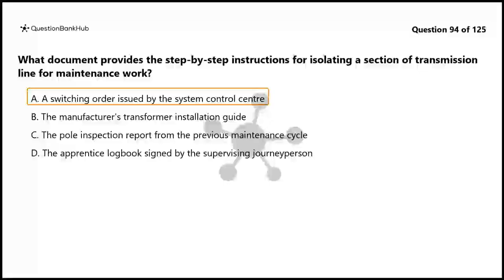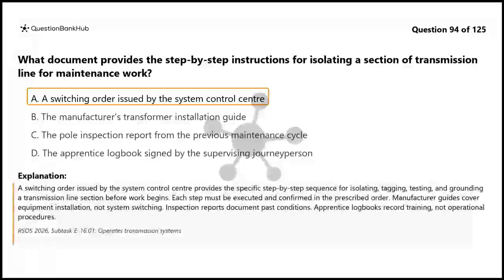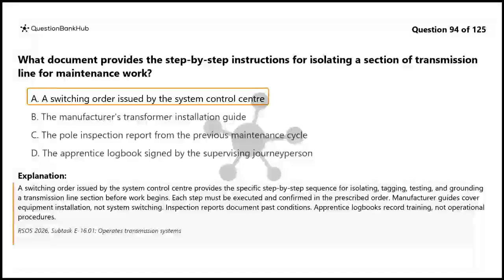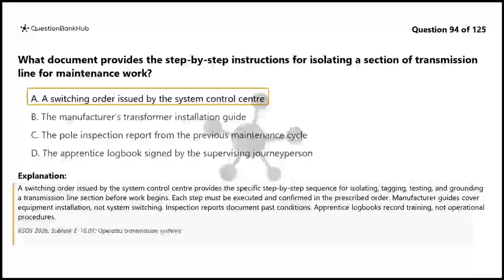The correct answer is A. A switching order issued by the System Control Center provides the specific step-by-step sequence for isolating, tagging, testing, and grounding a transmission line section before work begins. Each step must be executed and confirmed in the prescribed order. Manufacturer guides cover equipment installation, not system switching. Inspection reports document past conditions. Apprentice logbooks record training, not operational procedures.